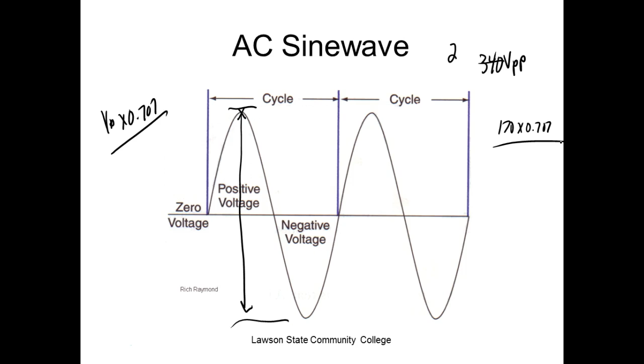Well, 120 is NEC, National Electrical Code, and they can't say exactly what you get, so they call it the nominal voltage. They use 120 and 240 as the nominal voltage, but odds are you're not going to get exactly those. We're pretty good here, we got 121 volts. But our power bill is going to be a little more than somebody getting 120 volts, because if the voltage goes up, the power being produced by all these loads is going to go up just a little bit.